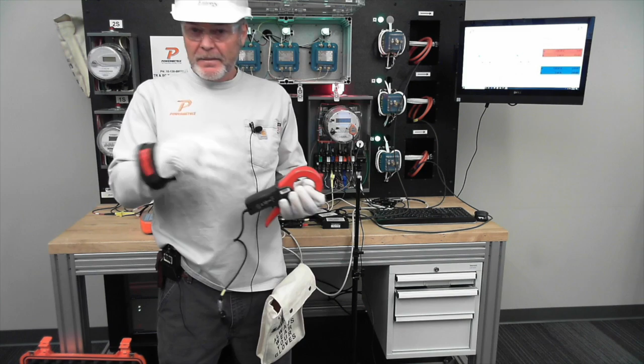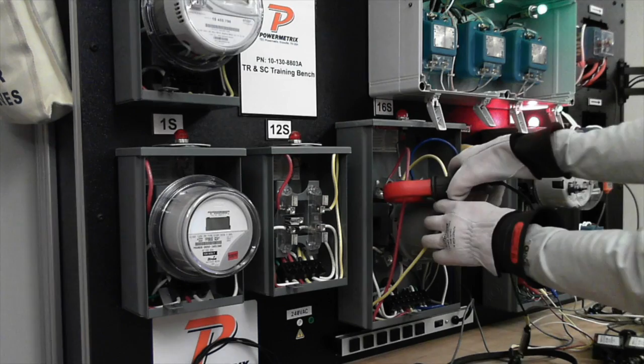These are the 752s that Chris showed you earlier. Remember, always look for the arrows — there's an arrow in here, and for us it points in the direction of the current, towards the load. On this 16 here, my current is coming, so I'd just connect it on that 16. This is rated up to 1,000 amps, so I'm fine on that. You can see you can fit some pretty decent sized stuff in the hole here. So when I've got a CT can right next to my transformer with one big conductor running through there, this is sweet — I just drop it on there. So this is the 752.